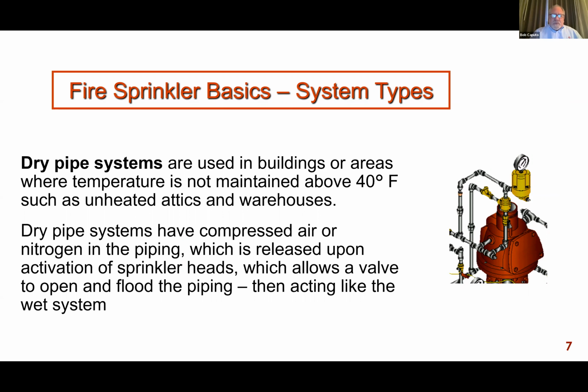When you have a tenant or a location where you can't maintain the building at or above 40 degrees, such as unheated attics and warehouses in, let's say, parts of Texas where freezing actually occurs, which is usually not Houston, a dry pipe system has compressed air or nitrogen in the piping. When the sprinkler activates, instead of the water instantaneously flowing like it does in a wet system, there's a delay in delivering the water because the water has to push the compressed air or nitrogen out. But then again, it operates just like the wet pipe system once the piping is flooded.